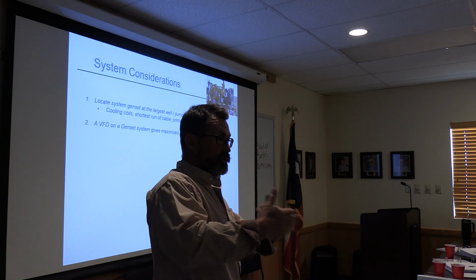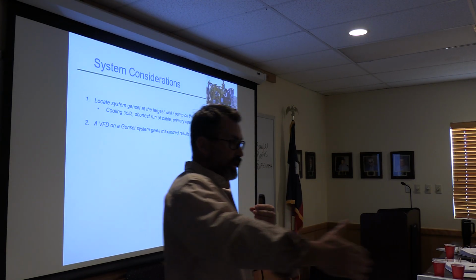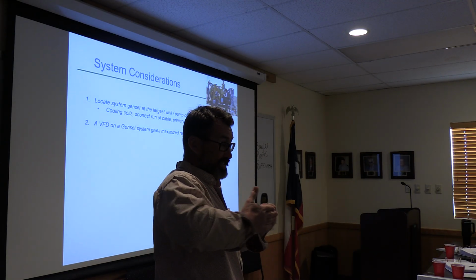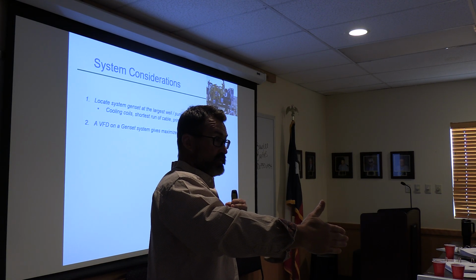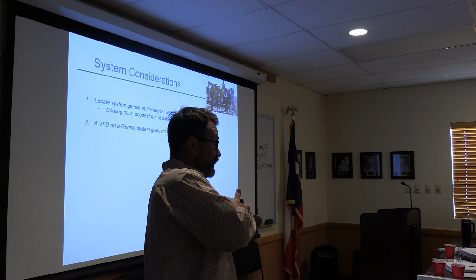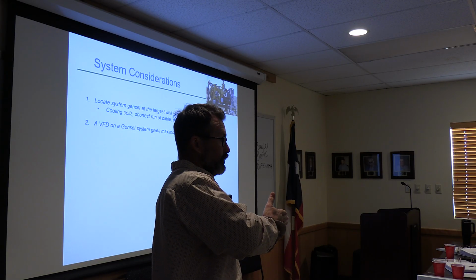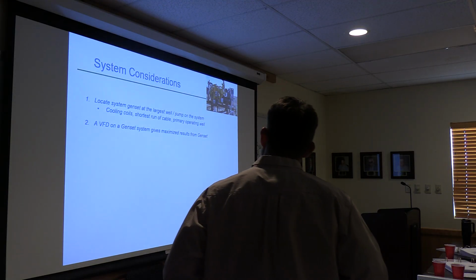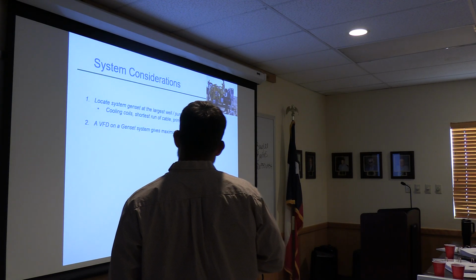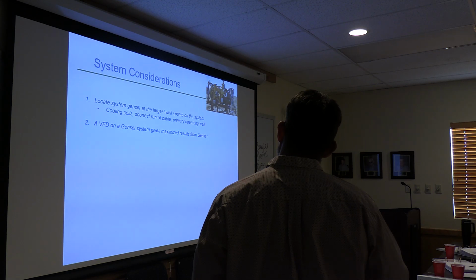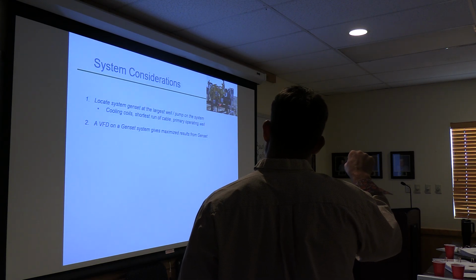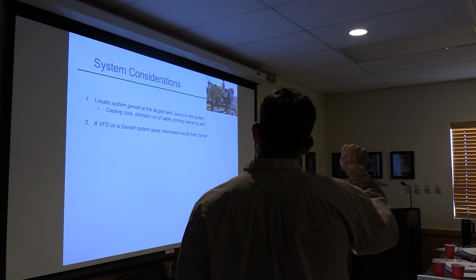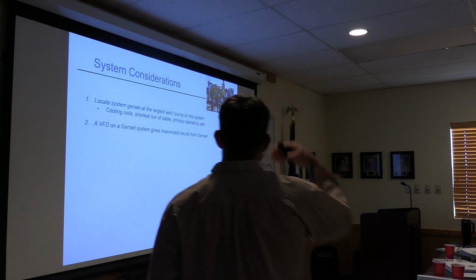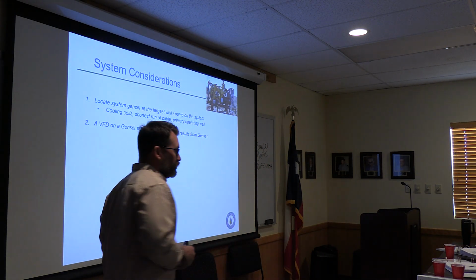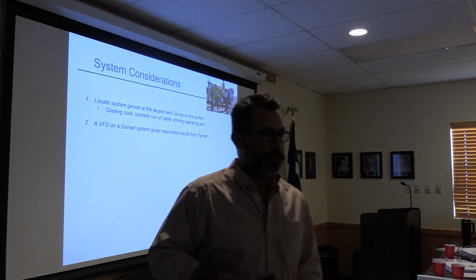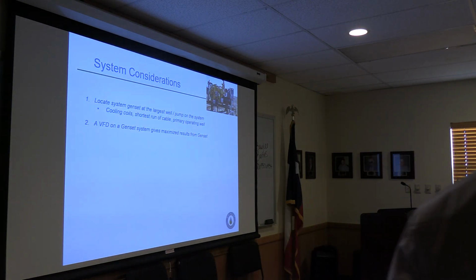And because there's a bridge rectifier in modern VFDs, it takes this bad power in, essentially disconnects it, and then realigns that power to something that's useful on the other side. And so what you end up with is much better control of your motors on the other side. Much longer lifespan of those components as well. We found that a VFD allowed us on this particular one, which is the case study here, the VFDs on those satellites allowed us to take this genset up to 100% of its service factor. You could run full capacity all year long, and we think the VFDs were a major part of that for a number of reasons.